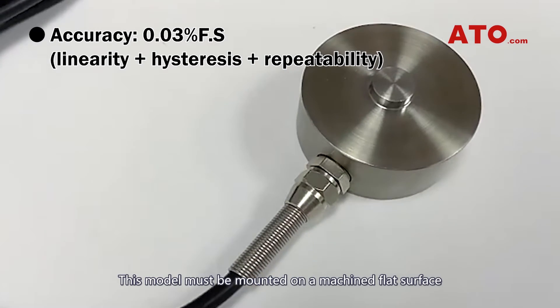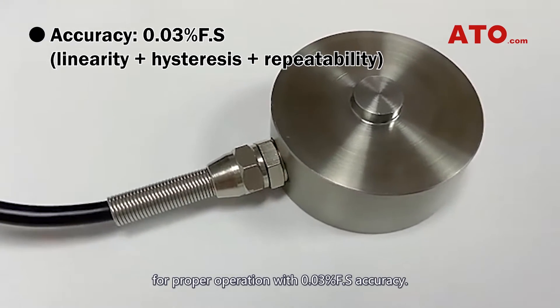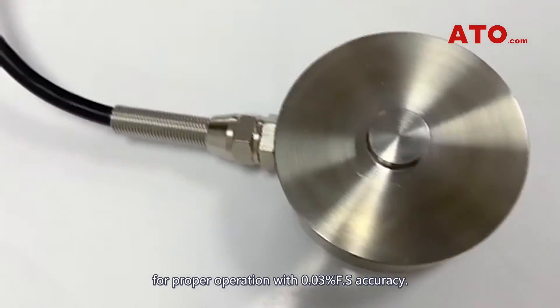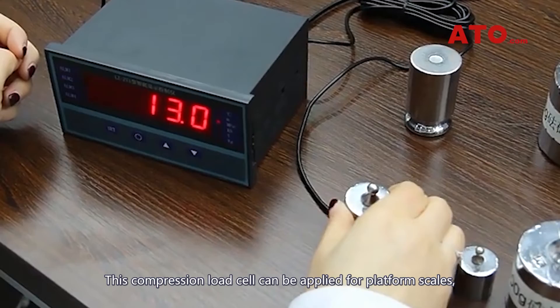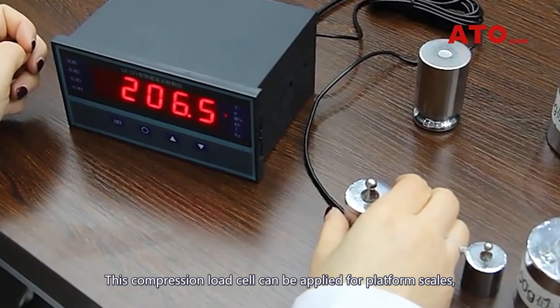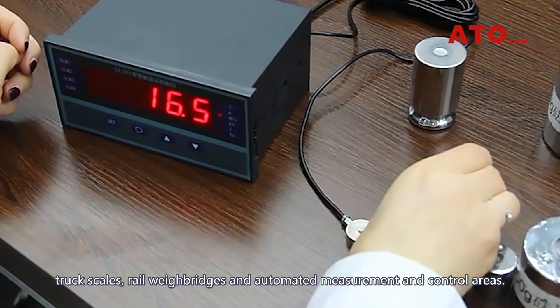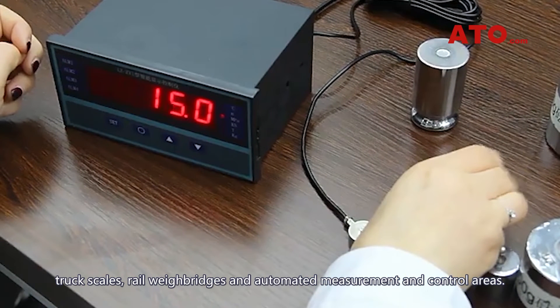This model must be mounted on a machined flat surface for proper operation with 0.03% full-scale accuracy. This compression load cell can be applied for platform scales, truck scales, rail weighbridges, and automated measurement and control areas.